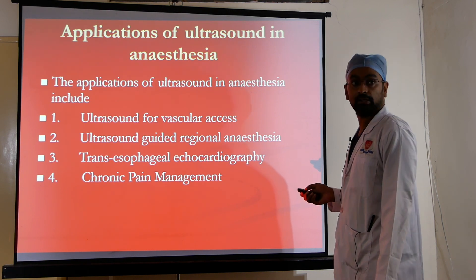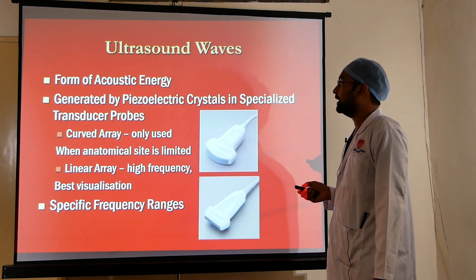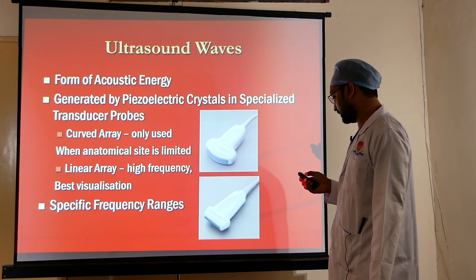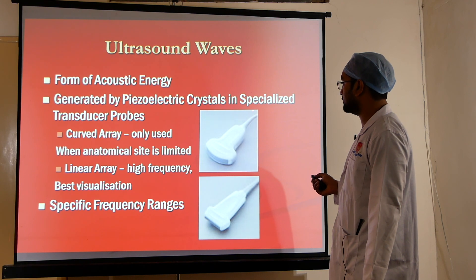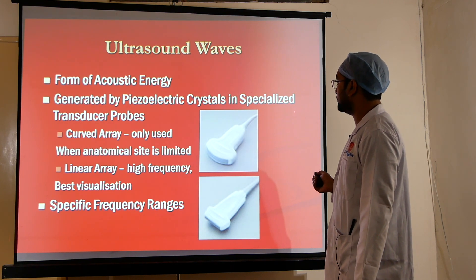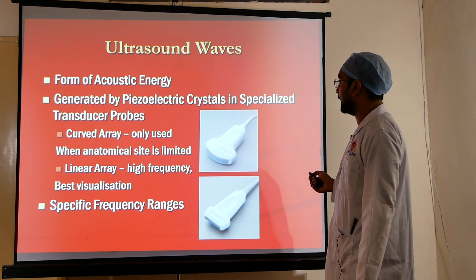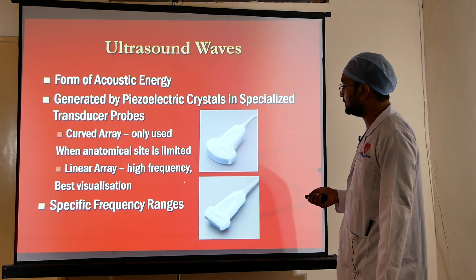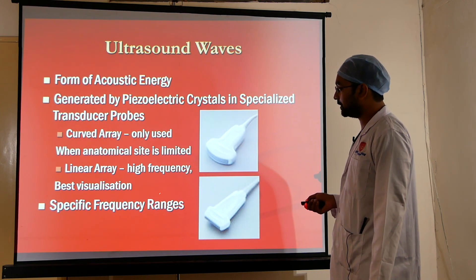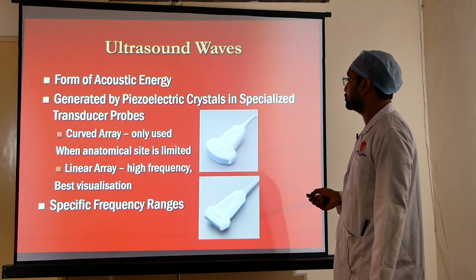Ultrasound is a form of acoustic energy. Ultrasound waves are generated by a piezoelectric crystal in specialized transducer probes. These probes convert electrical energy from the machine into mechanical energy, send this energy to the body parts, and according to the frequencies reflected back, generate an ultrasound image.